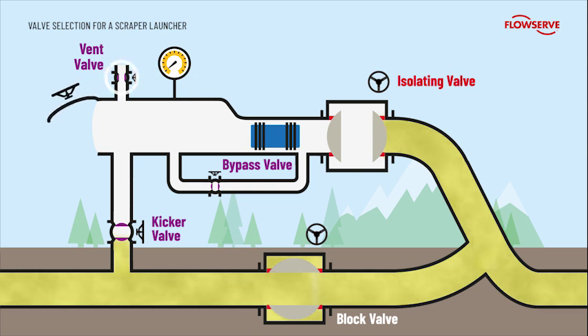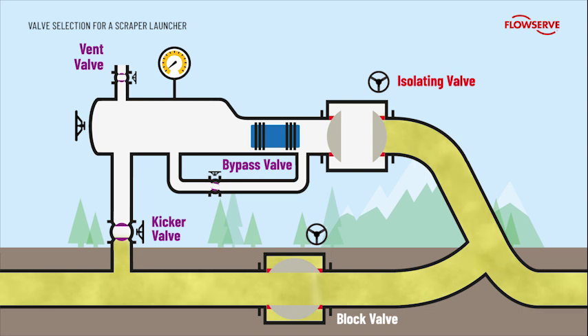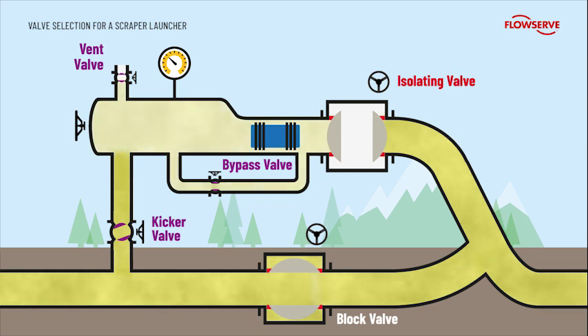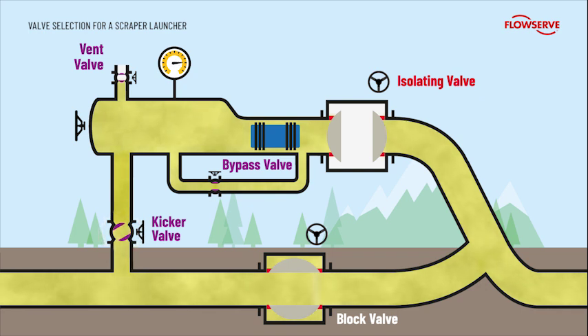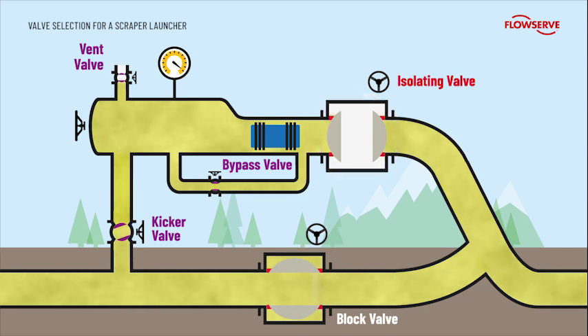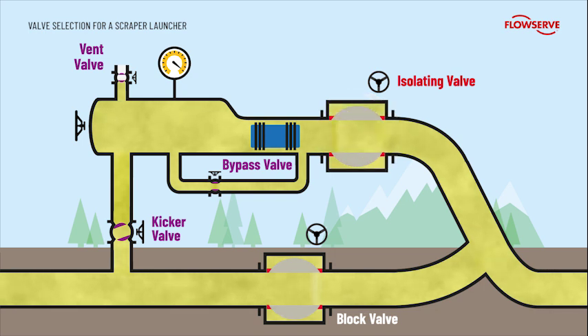The vent valve and chamber door are closed and the bypass valve is opened. The kicker valve is now slowly opened to pressurise the chamber and balance the pressure either side of the isolating valve. The kicker valve is rarely fully opened, as throttling of the gas flow provides control over the speed of the scraper when it moves into the pipeline. Throttling would damage a soft-seated ball valve, hence a plug valve is used. The isolating valve is generally a full-bore, soft-seated ball valve to allow the scraper to pass through, and with the pressure now balanced either side, it can be safely opened without damaging the seats.